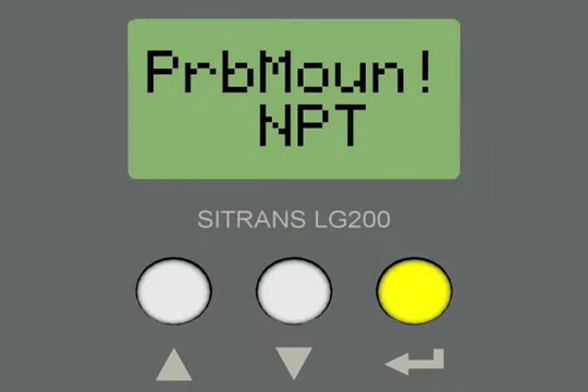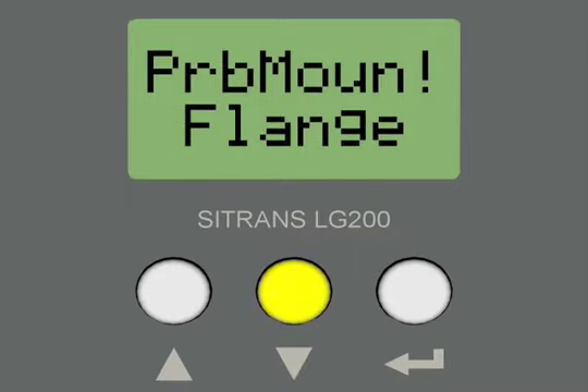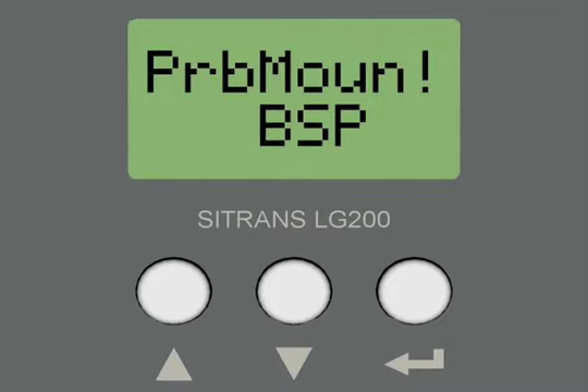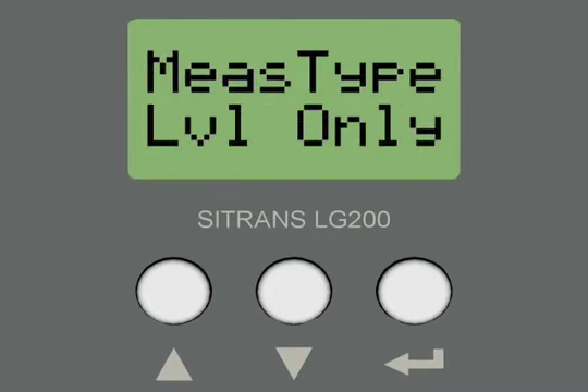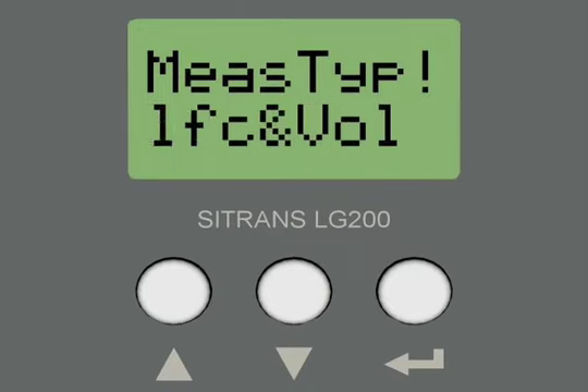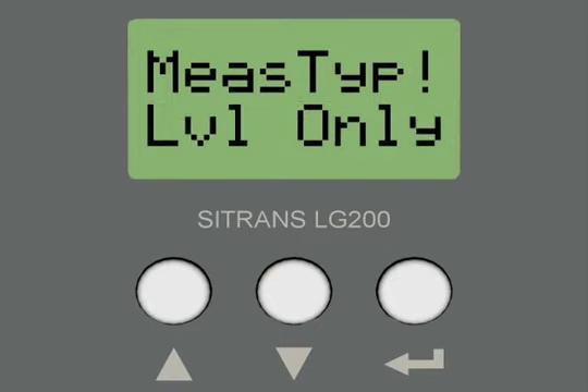Push Enter to edit the probe mount parameter. Push the down arrow key twice to select the BSP mounting option, then press the Enter key. The next parameter is the measurement type parameter. Press the down arrow key to go to this parameter. There are 4 measurement type selections: level, level and volume, interface, and finally, interface and volume. In our application, we want the display to indicate level only. Since this is the default setting, we can now proceed to the next parameter by pushing the down arrow.